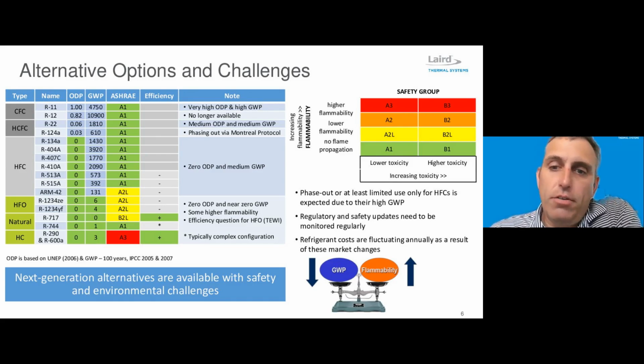The first character, the letter in the code, indicates the toxicity, so whether it's an A or a B toxicity class. And then the higher the number, the higher the flammability in the second character. So as we go from an A1 up to an A3. And you can see that, when we look a little bit closer at the table on the left, there's certainly a balance between the flammability and the global warming potential of the refrigerants. As the global warming potential goes down, there tends to be a higher flammability rating.